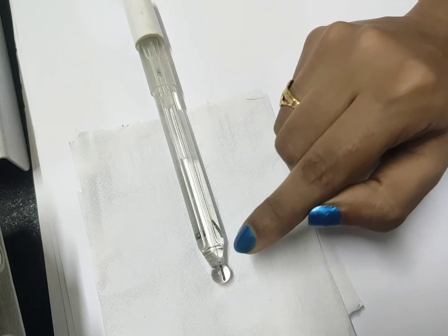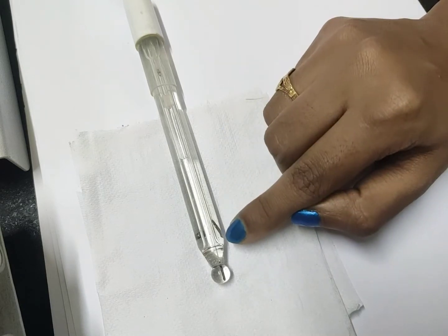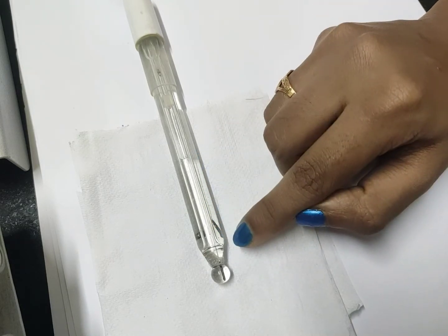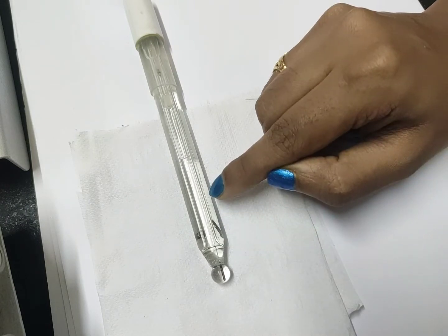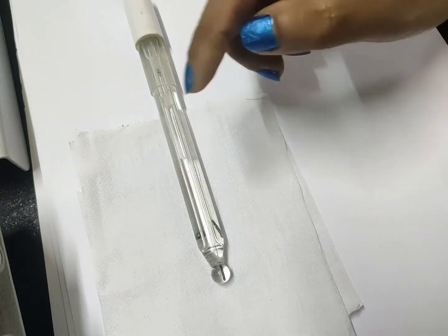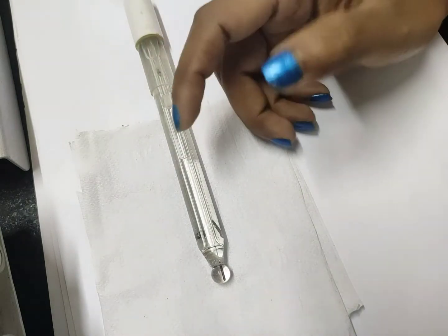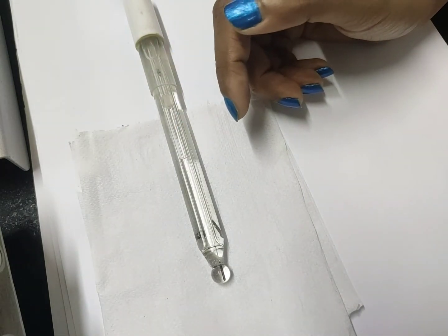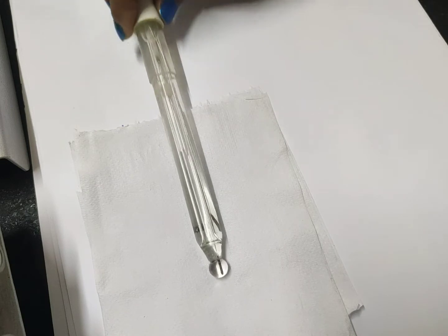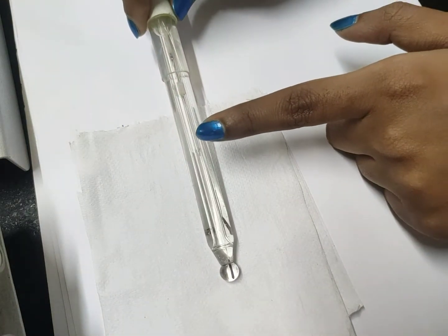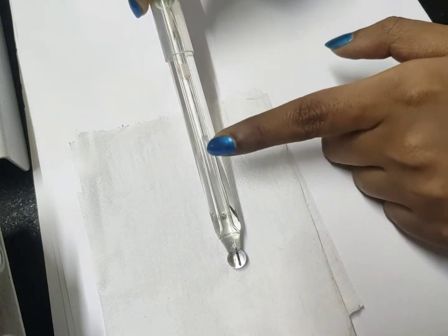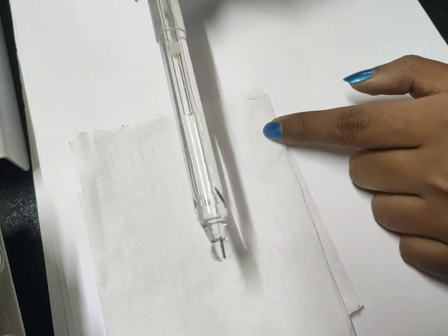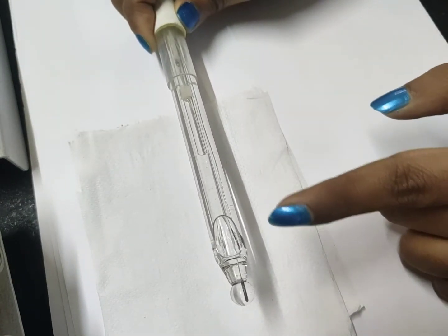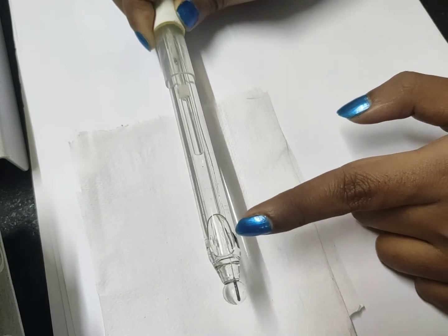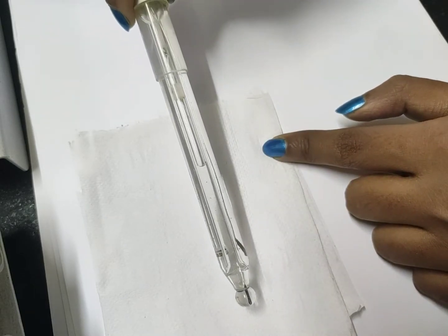Also if you pay attention, these two are in different chambers. These two do not come in contact with each other, whereas both are filled with another internal solution, which is mostly 0.1 normal hydrogen chloride, HCl, solution. So you can see it is filled with liquid. For the inner bulb the liquid is here, and also for this part. Now you can see the electrode present in this solution is here, so the electrode is filled with the internal solution like this.